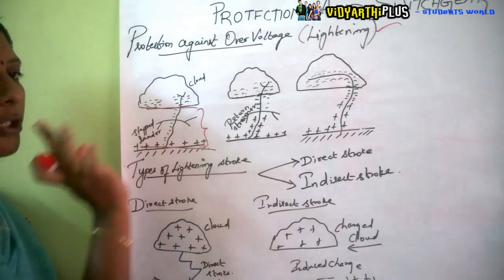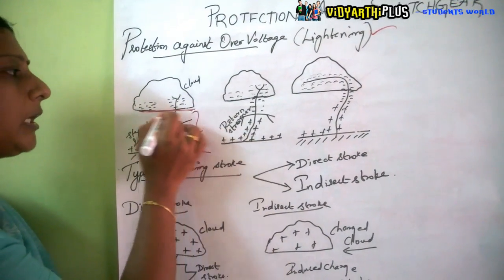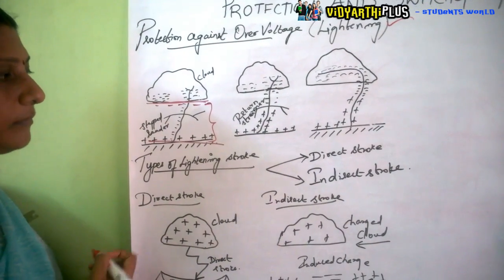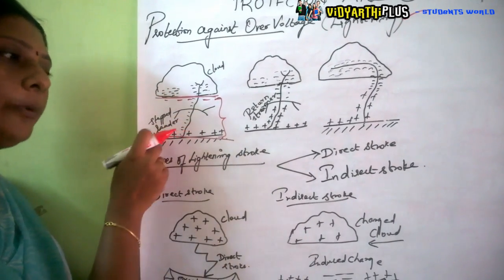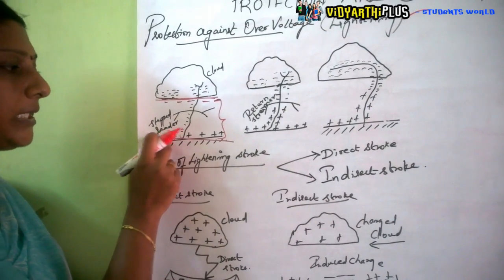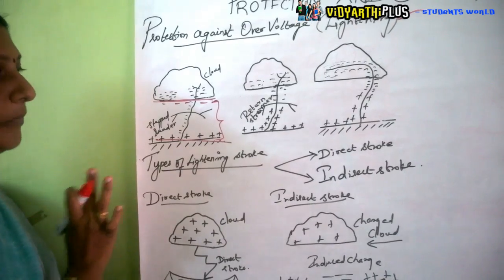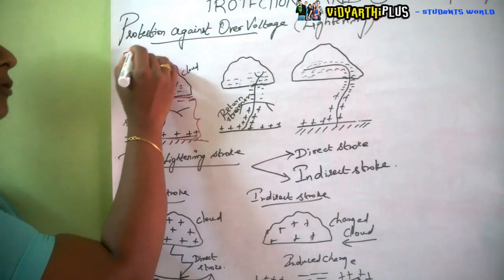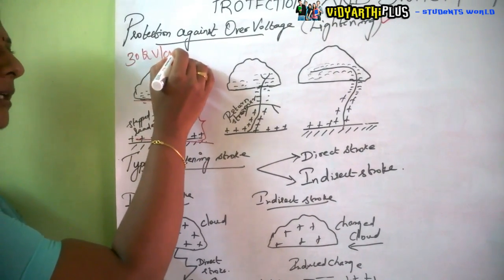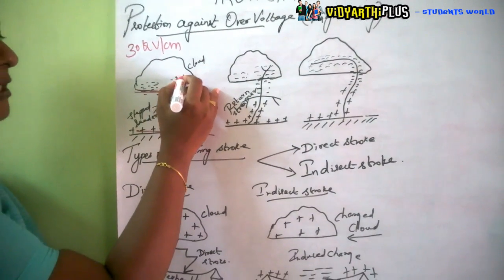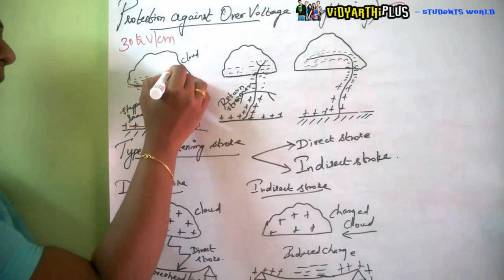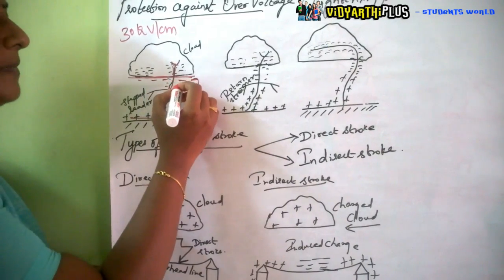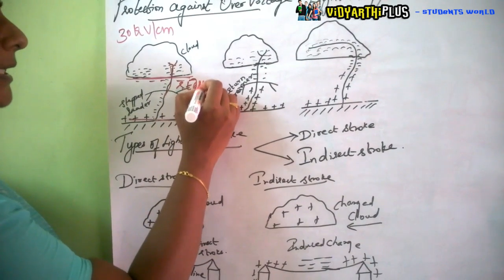Assume that the cloud carries negative charge, so the bottom of the cloud is occupied with negative charges. Immediately, the opposite charge — positive charge — accumulates in the ground. When the potential gradient exceeds 30 kV per centimeter, the negative charges start coming down in what is called a stepped leader.